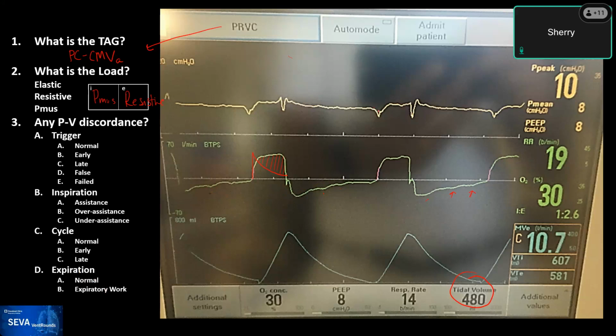She does have discordance. There is a little bit of a delay before the breath actually starts. But it's not so big. You don't start to see the real dip until, yeah. So I guess you could argue that it's late. It seems pretty quick, less than a quarter of a second, but that big dip could also be another 20 or 30 milliseconds with the PMUS too.